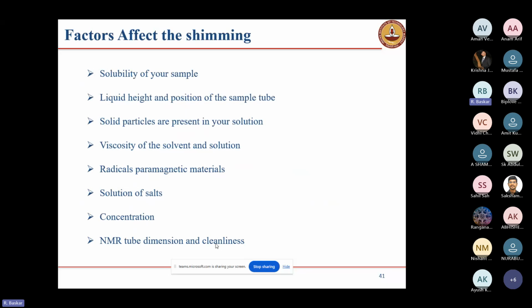Viscosity: if your solution is more viscous, that will also affect the shimming. If radical or paramagnetic impurities are there, that will also affect the shimming. If your solution has the salt of some of the compounds, then that time also it will affect the shimming. Concentration, as I already told, for proton NMR, if you are taking more concentration, you will get bad shimming, you will get broader signals. NMR tube dimension and cleanliness will also affect the shimming.